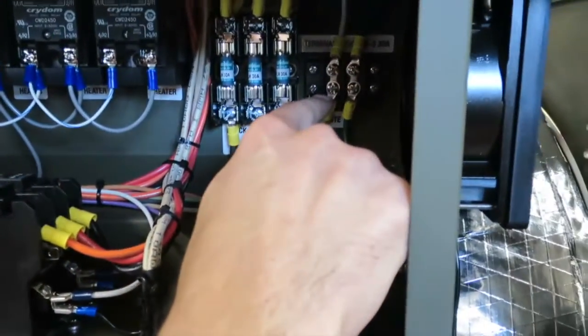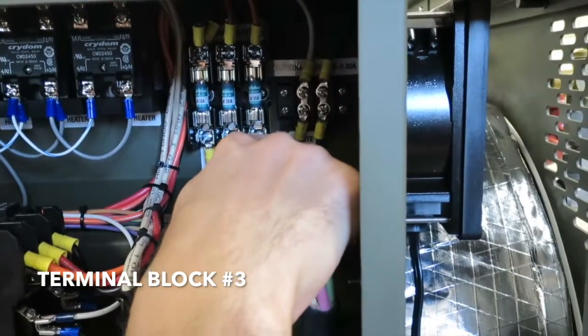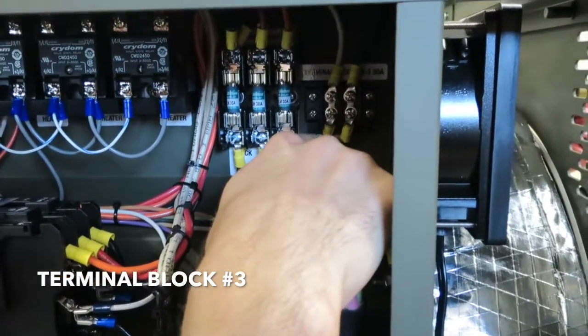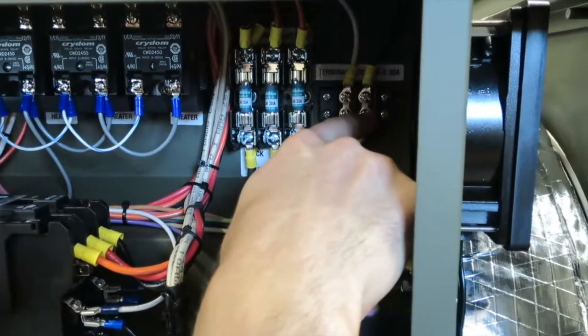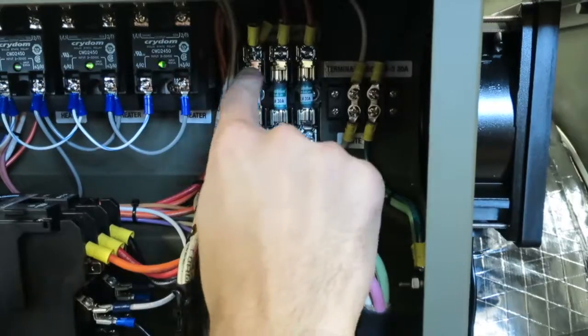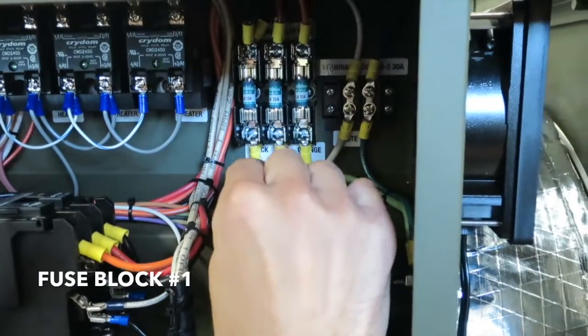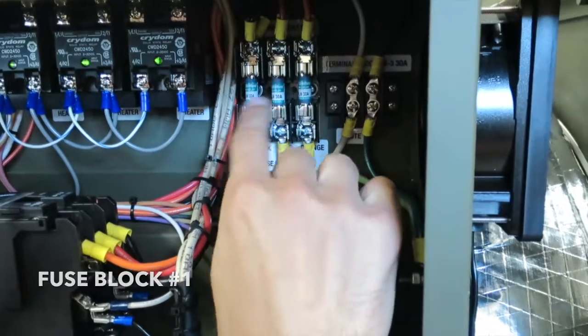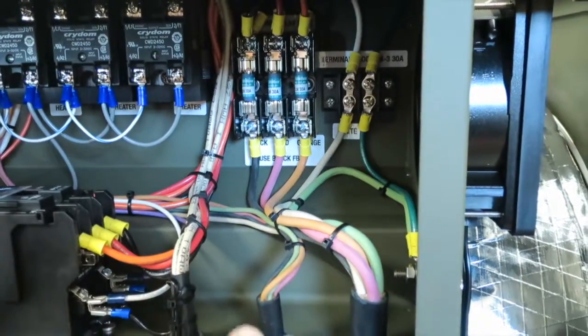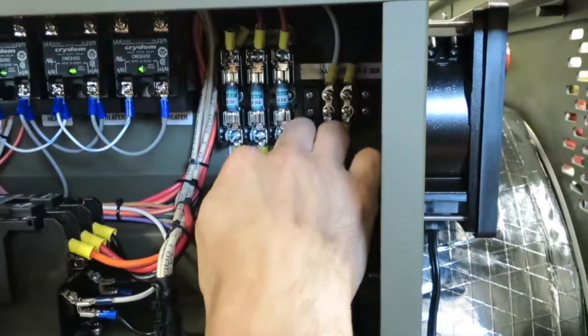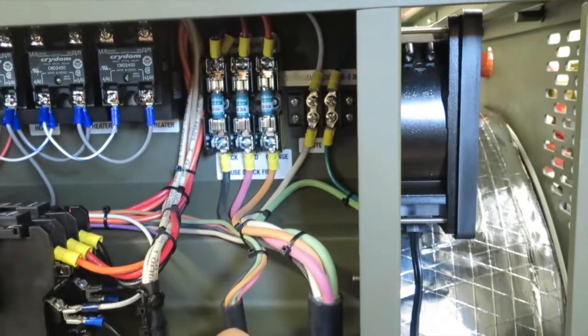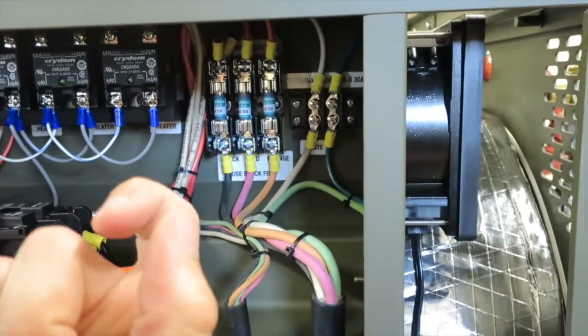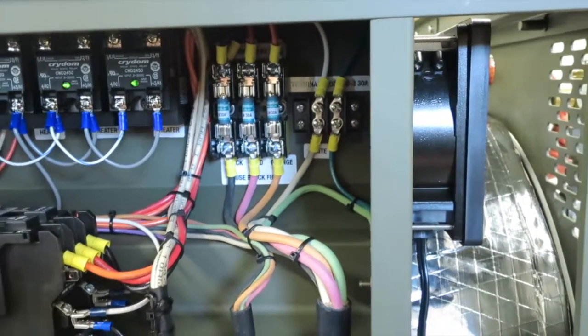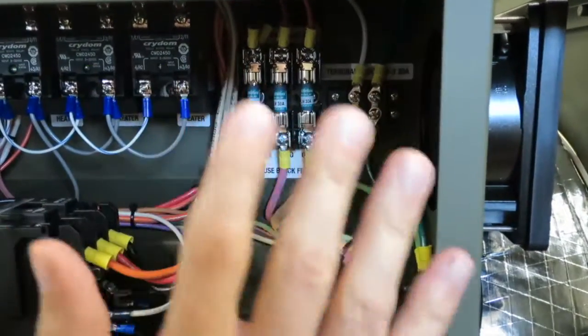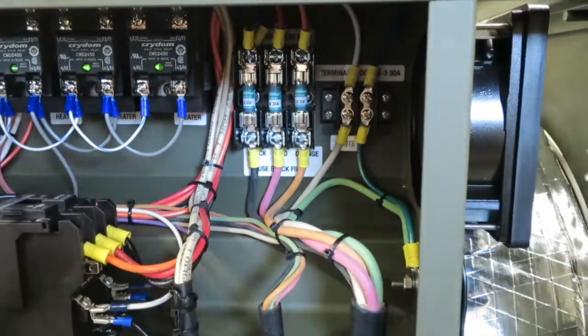Right here we have terminal block number 3, which is just to connect the neutral and the ground, the green wire. So that is terminal block number 3. Right here we have fuse block number 1. So these are 30 amp slow blow fuses. They're all the same. There's one fuse per phase of 208 coming in, so we got 3 of those. Those just kind of lock in and out and you kind of pry them out. But again, remember never to touch this area if the unit's on. All that maintenance has to be done with the sterilizer off and power disconnected.